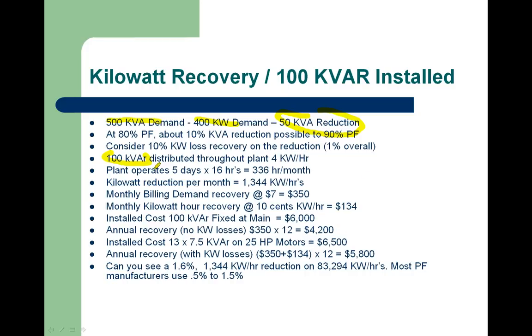So if we take a plant that operates 5 days a week and 16 hours a day, we end up with about 336 hours per month. Now, for our kilowatt reduction per month, if we took 4 kilowatts per hour times the 336, we could end up with as much as 1,344 kilowatt hours per month in I²R losses.